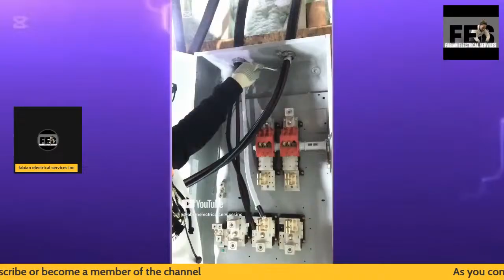In today's video, what I'm doing is grounding off my ground wire onto the ground bushing, ground clamp on the TECK cable required by code. It has to be grounded off because of the cable that I use.